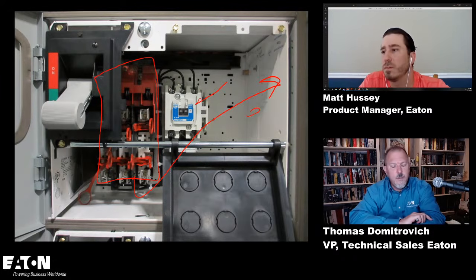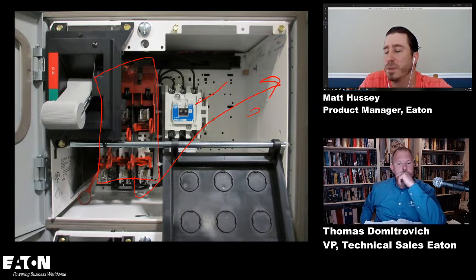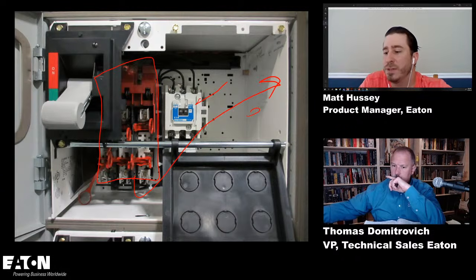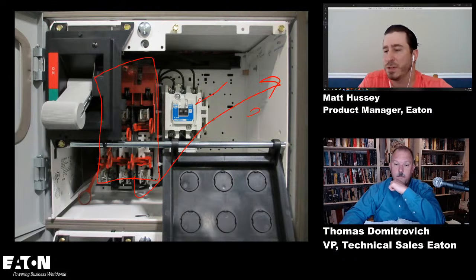I can't think of any, like a fusible area versus a breaker area, but suffice it to say you have to consider not only the components but the volume it's installed in. Right? Because temperature rise and short circuit are all things that are also described for a certain space. So you couldn't just automatically upsize. Say I've got a 10 horse application and I want to upsize it to 15 or 30. I might be able to fit those, but over time the size is also a consideration, because it needs a certain amount of space for temperature performance as well as short circuit.